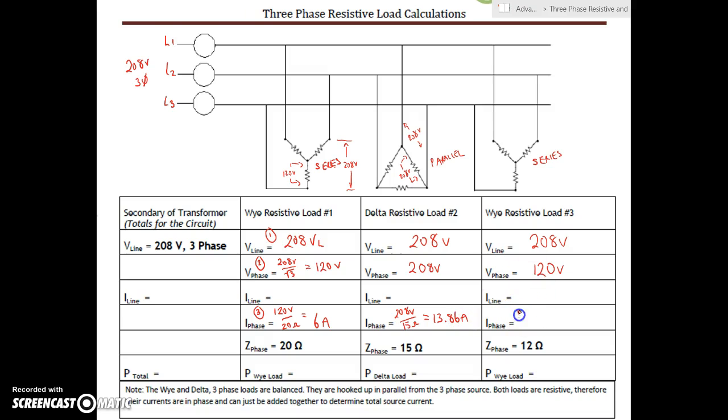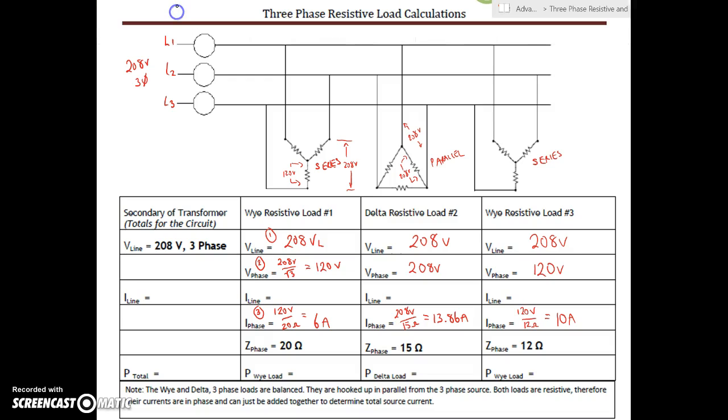Each of these are balanced circuits, so each of those resistors is 15 ohms. So we now have 208 volts over 15 ohms, that gives you 13.86 amps. Next one we've got is 120 volts divided by 12 ohms, and that's obviously going to give us 10 amps. Now we're keeping track of all of our currents there. So inside this guy, we've got 10 amps on the phase.